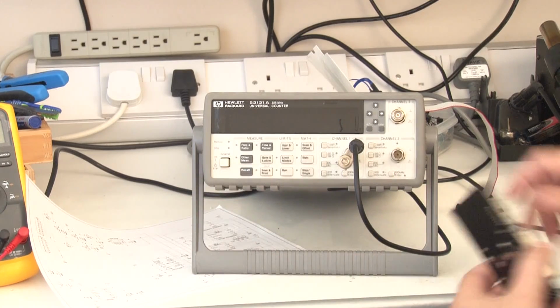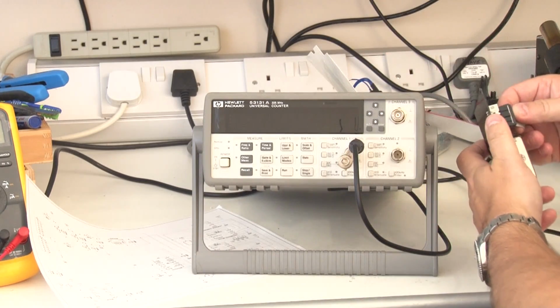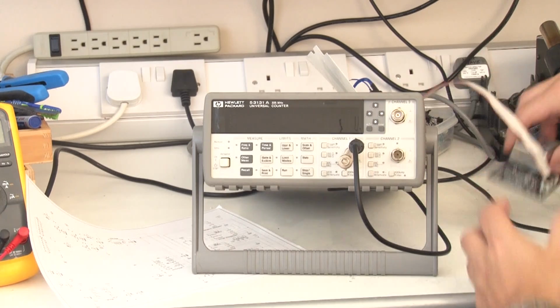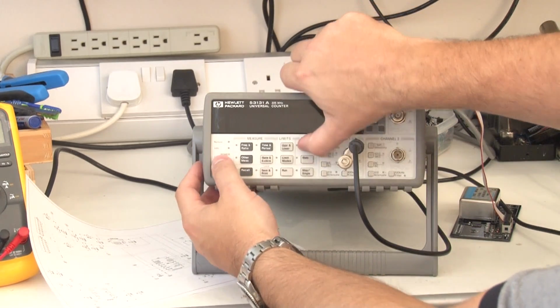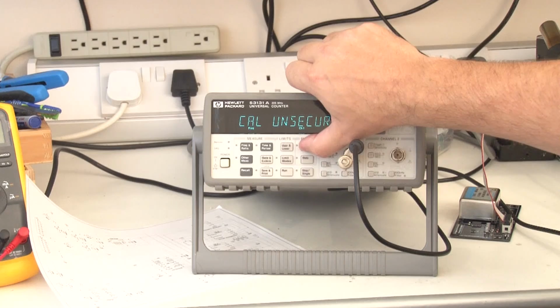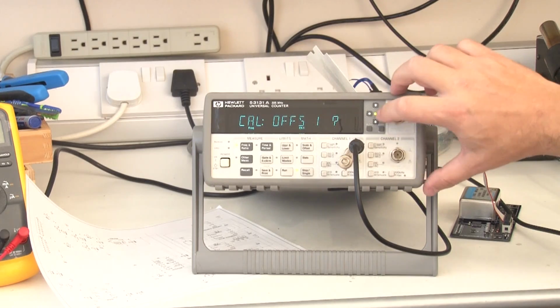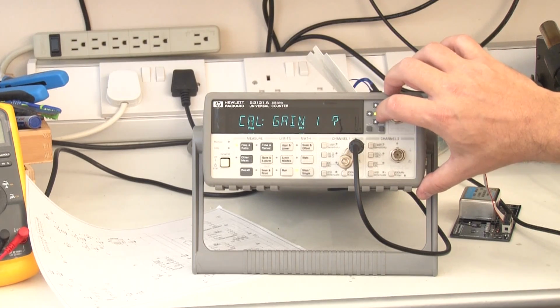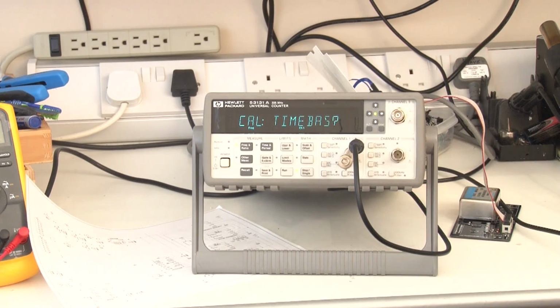Now if I power that down, once the option's fitted, it should detect that it's there, and I should have the option to calibrate it. So now we've got offset 1, offset 2, gain 1, gain 2, TI quick, TI fine, and cal timebase.